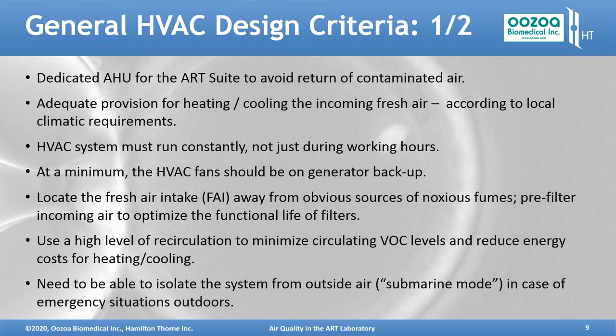This is often called submarine mode, in case you have an emergency situation outdoors, like a bushfire or a sandstorm, or something more everyday, like someone re-tarmacking the parking lot next door to your building. So in those situations, you will need to be able to isolate the clean room. You will probably lose the ability to maintain the overpressure, but at least you won't be putting the contaminants into your space.